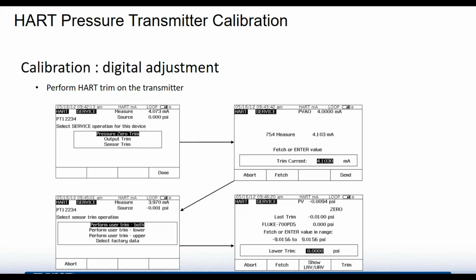Second, you want to go ahead and do your sensor trim. So with the 754, you can trim both your upper and lower values. So you go in and put in the 0, open to atmosphere pressure at 0, trim it so that it matches up, and then you'd pump the pressure up to the upper end, which in this case was 5 psi, pump the pressure up to 5, and trim it to that. So that now you've got your sensor trim adjusted and your 4-20 trim adjusted.